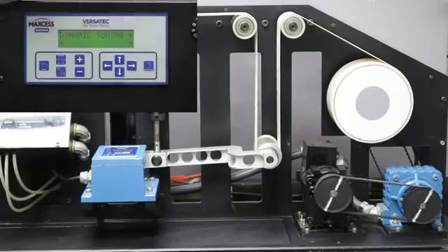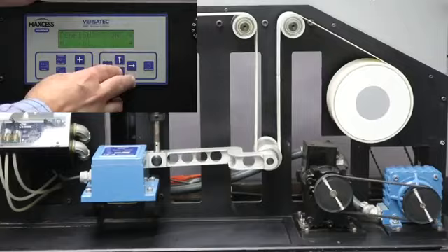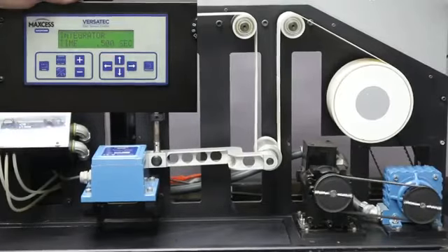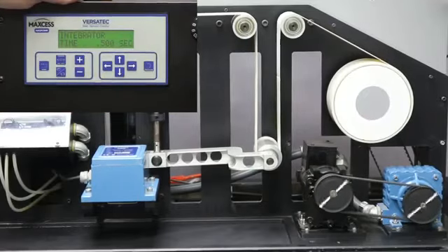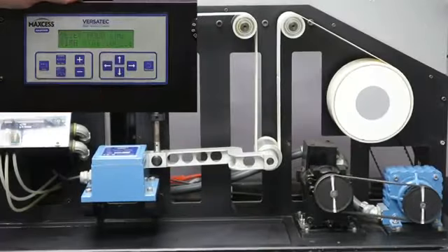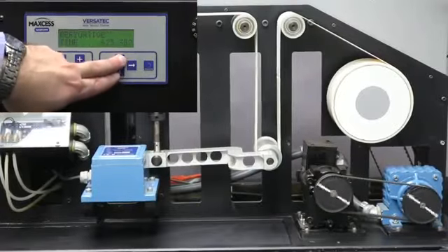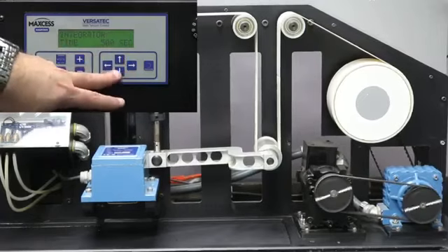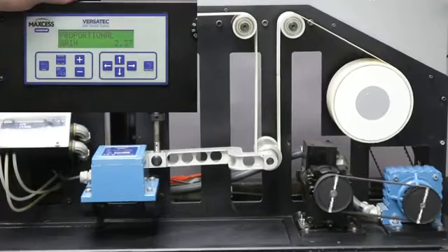Now, if I was a control expert, I can go into configuration, and there are multiple things in here that you can do. We talked about the different features and things that you can add to it, like the sensors and the current to pressure transducer and the gain scheduling. We're not demoing all of that right now, but I do have direct access to the integrator, the proportional gain, and the derivative. You can see right now my integrator ended up at 1/2 second, so it's going out and looking for an error every 1/2 second. Our proportional gain ended up at 2.37.